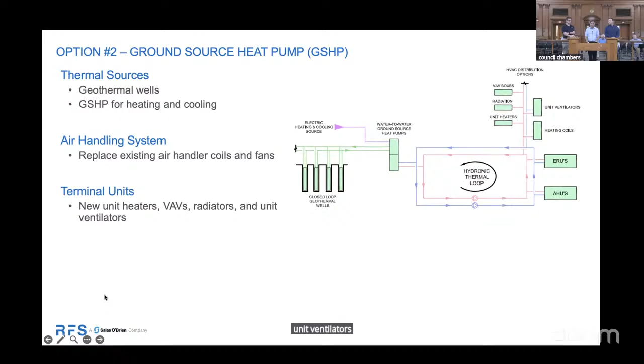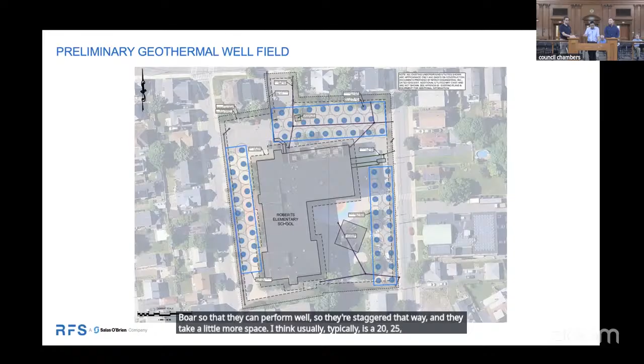Will you go on to the next slide, please? That shows about 60, plus or minus, geothermal wells intended to be about 800 feet deep into the earth, and they're staggered. One key note about the geothermal wells is that the actual bore is roughly 8 to 10 inches round, but because they're a heat sink, they require more separation between each bore so that they can perform well. So they're staggered that way, and they take a little more space. I think typically it's a 20 to 25 foot diameter around them.